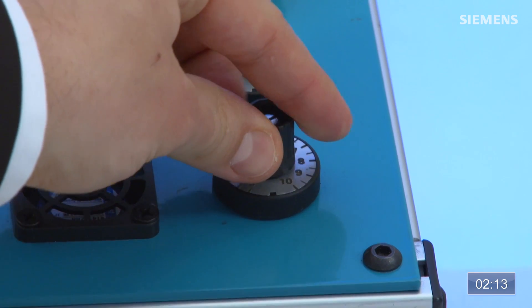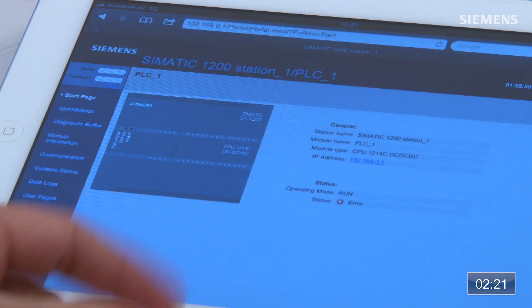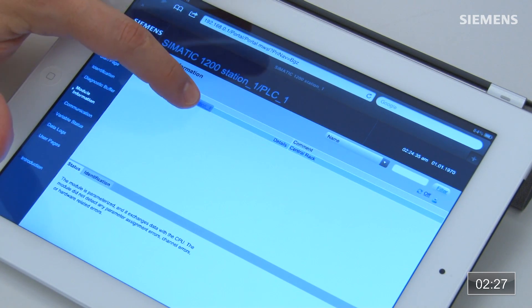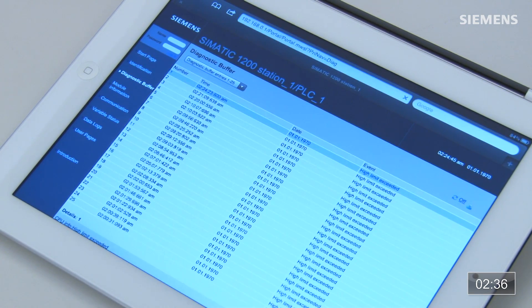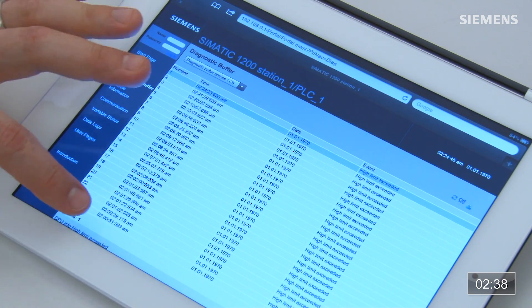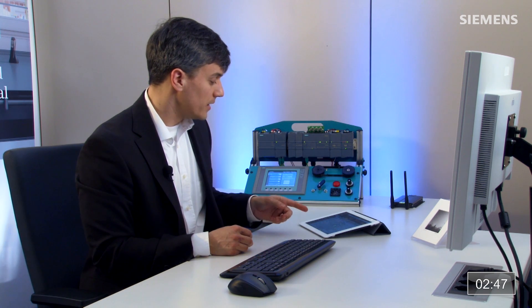We can actually create faults. With this automation system, if I turn the potentiometer to create an analog fault, I notice status LEDs appear on the first page indicating something is wrong. Going to the module information page, I see a red wrench — clicking on that tells me the analog module has something wrong. Then in the diagnostic buffer, just like in the engineering system, I can see I have a high limit exceeded on channel zero. Once I identify and solve the physical problem, the web server will show the fault has been resolved.